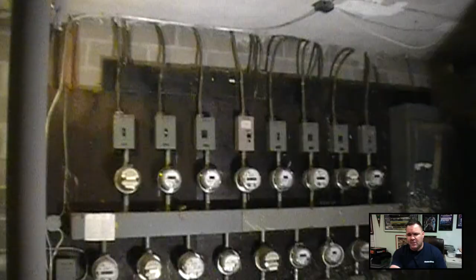So here we are - I don't know what happened with the video, but I did not record myself putting the circuit breakers in. The breakers are in now, and all the wires have been terminated. I'm going over here to the main breaker for that apartment and turning it on before I go upstairs. There's a good look at all the mains feeding the apartments in that building, with the main disconnect on the far right.